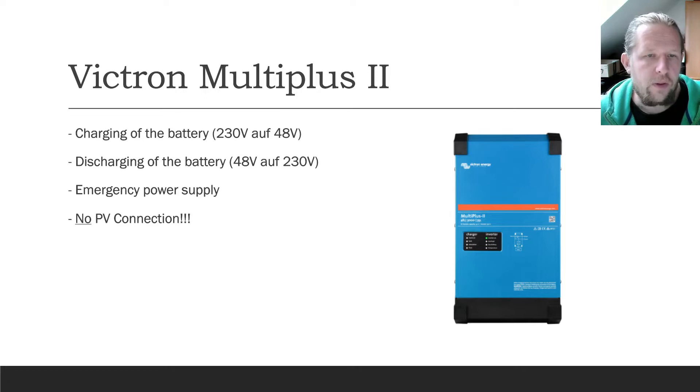An additional essential thing of this system is the Victron MultiPlus 2. It has multiple functions. It can charge the battery from 230V to 48V. Also it can discharge the battery from 48V to 230V. It brings the functionality for the emergency power supply. It can make a grid for us even when the public grid is not available. But an important thing is that it does not have any photovoltaic connection. So we have other alternatives that I will show you next.